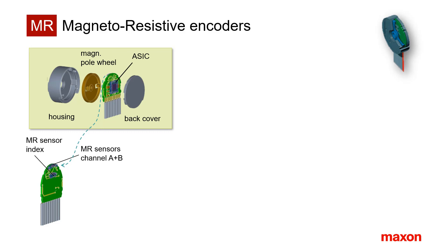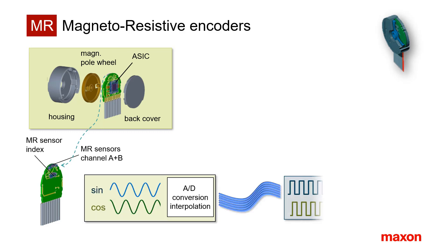MR uses the fact that in certain thin film materials, the electrical resistance changes with the relative direction of current flow and magnetic field. The multipole magnetic pole wheel mounted on the motor shaft creates the necessary magnetic field changes at the sensor positions. The MR sensors are designed to create sine and cosine type signals for each magnetic pole, which are further processed to generate the typical rectangular incremental encoder pulses. The resolution depends on size and interpolation.